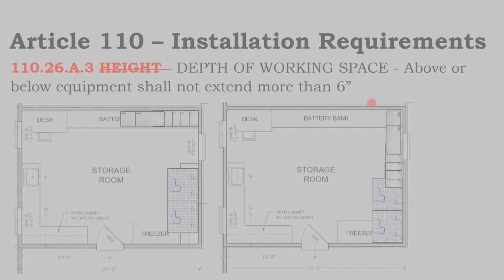And so, the reason why this would be a violation, going back to our spec sheet, is this equipment only sticks out 9 inches from the wall, and these batteries stick out 38 inches from the wall.